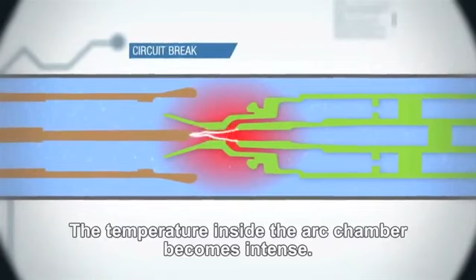Another consequence of the heat, the pressure of the gas increases. The movement of parts in the arc chamber also contributes to this rise in pressure, just like in a bicycle pump. Under pressure, the gas escapes from the center of the arc chamber towards the bottom of the chamber, drawing the arc with it. The electrical arc is extinguished. This gas is replaced by cooler gas in the central zone. The SF6, thus cooled, rapidly recombines and recovers its insulating capacities.